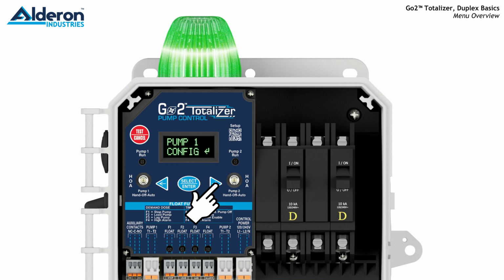Under Pump 1 configuration, you can make changes to the following parameters. The parameter called Pump 1 Enable can be changed to disable Pump 1 so that it will not run in either hand or automatic mode. The parameter called Current Sensor can be either enabled or disabled. Under High Amp parameter, the alarm activation and pump cutout feature can be changed from factory default setting of 25 amps. Under Low Amp parameter, the alarm activation can be changed from factory default setting of 1.2 amps.